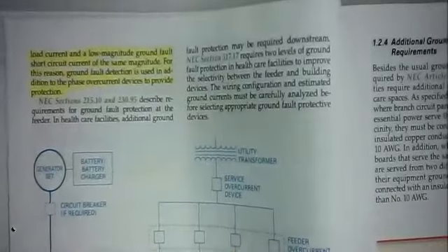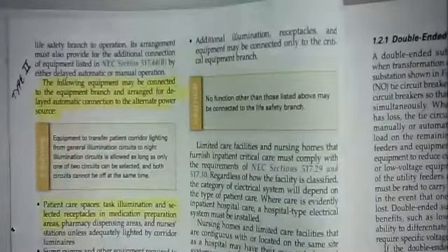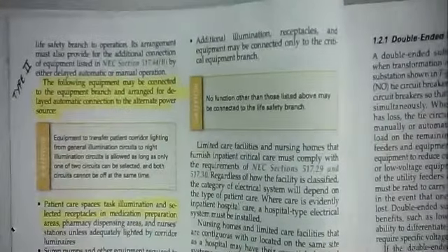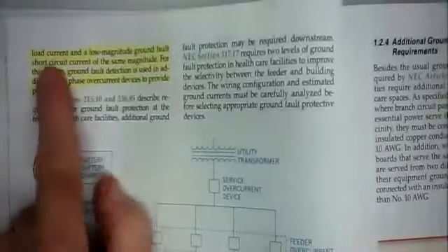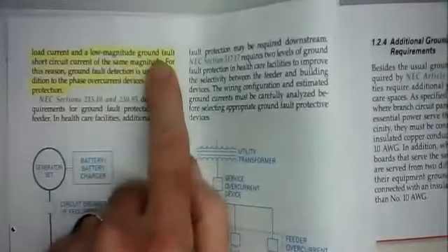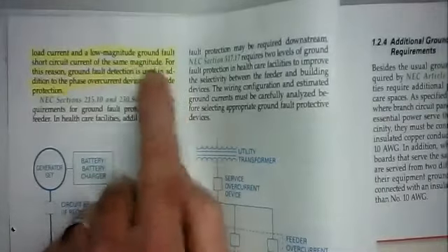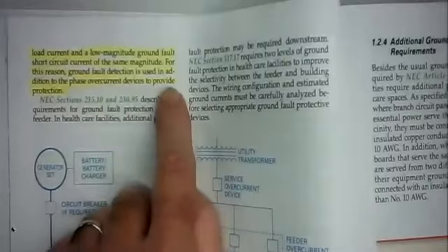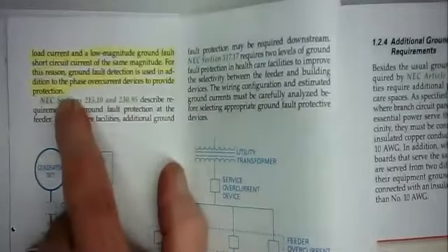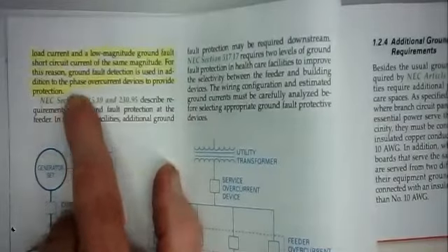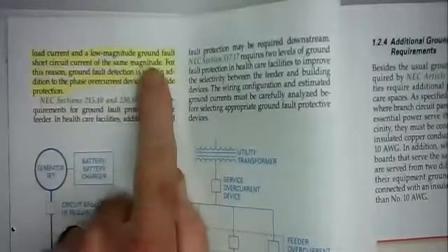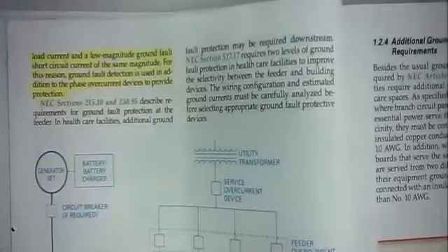Oh, this is the continuation of that one sentence that said phase overcurrent devices cannot distinguish between normal load current and a low magnitude ground fault short circuit current of the same magnitude. For this reason, ground fault detection is used in addition to the phase overcurrent device provided to provide protection. So they're going to have a ground fault circuit interrupter for low magnitude ground faults.